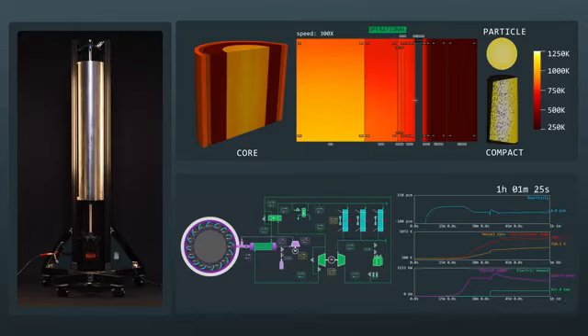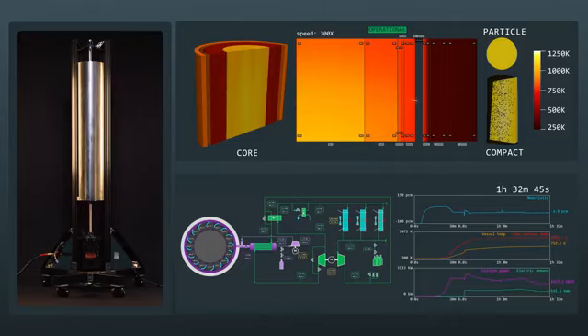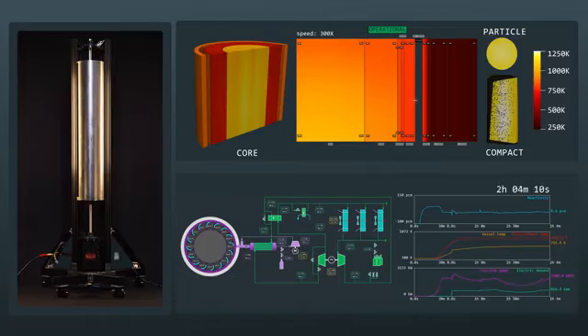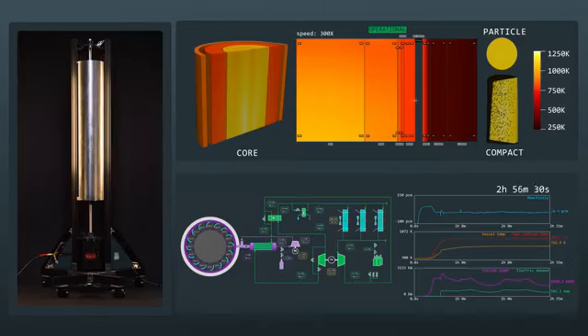The turbo machinery ramps up to speed as the core reaches target temperature, and a circuit breaker connects the microgrid electrical load. Unlike traditional nuclear power plants, Kaleidos is capable of rapid load throttling, or efficiently following a fluctuating electric demand. This is accomplished by adjusting the machinery shaft speed, the helium mass flow rate, and by continuously moving the control drums to modulate core heat generation.